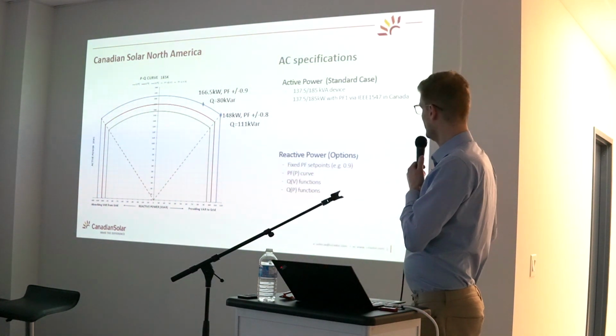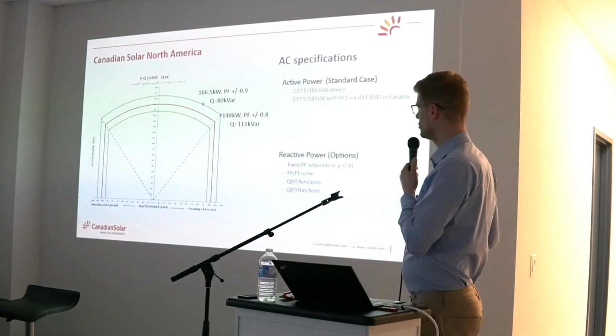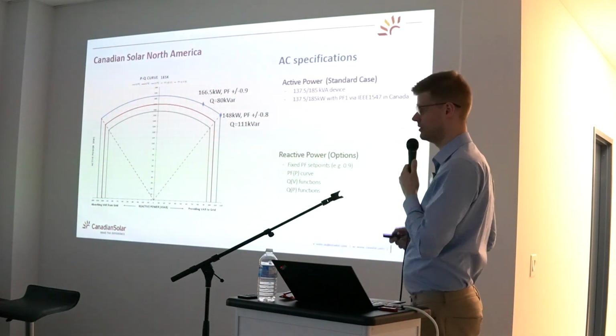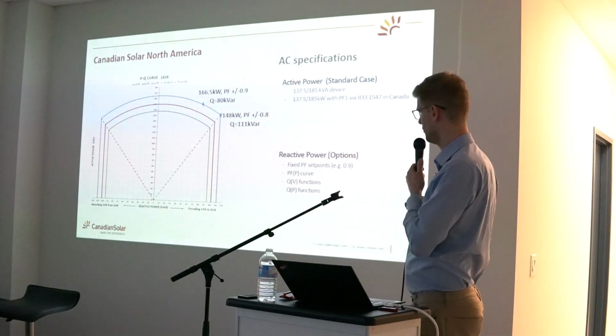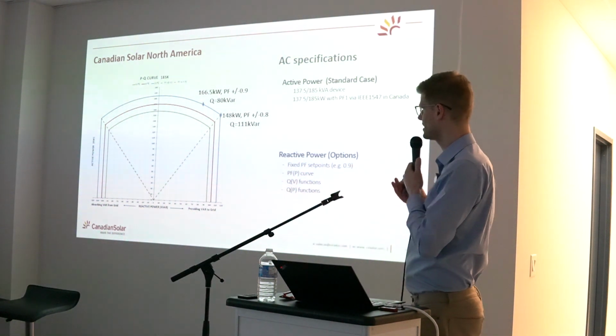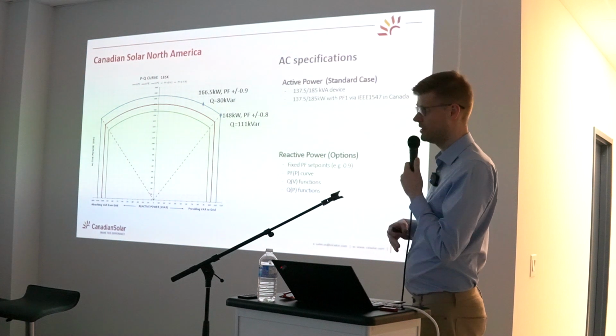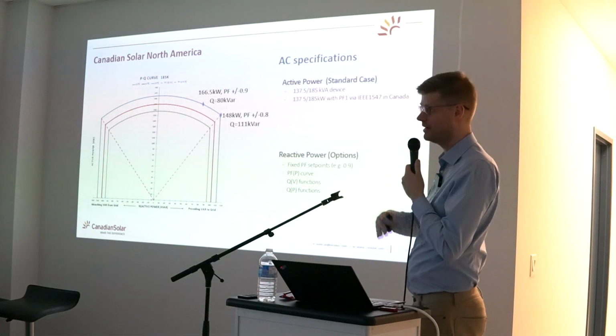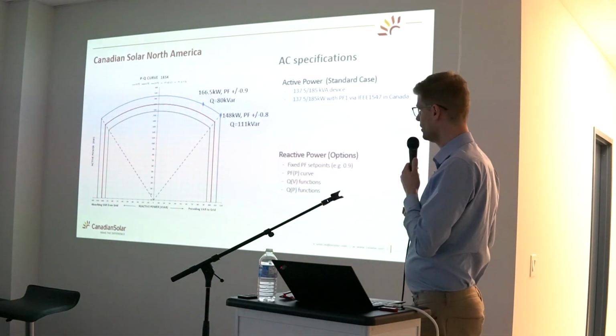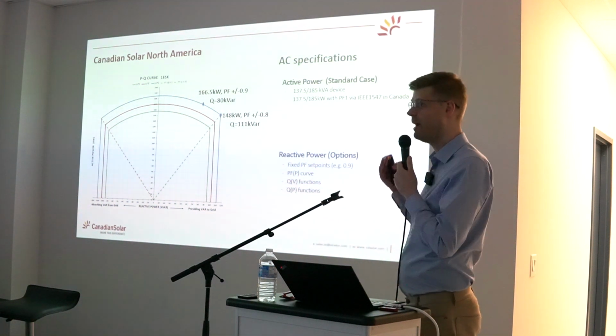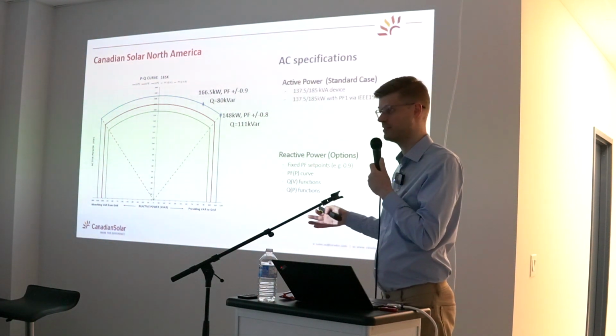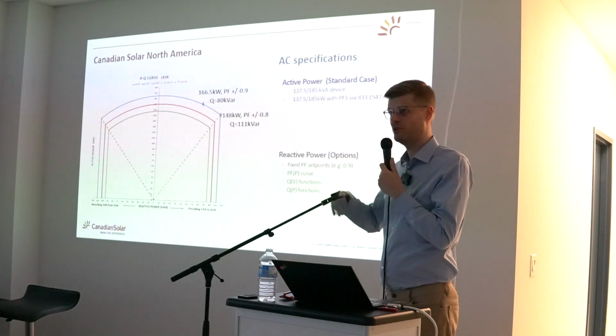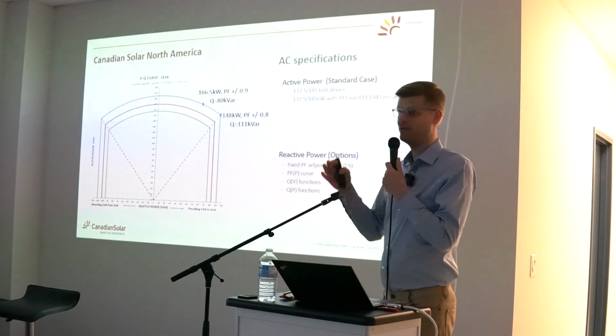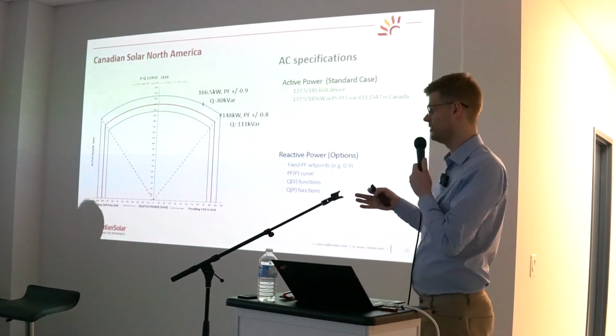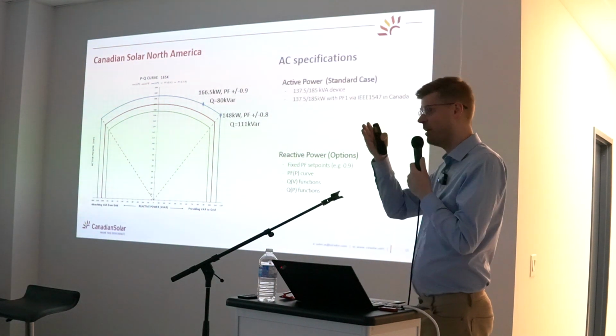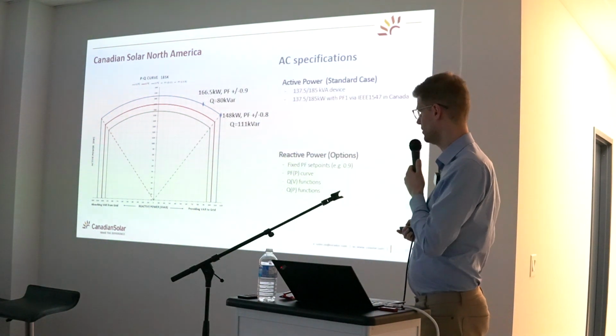The options you have available to use that power factor or that reactive power output are, the first one I just talked about, the fixed power factor setting. So the utility company just tells you 0.9 it is, and you have 0.9 whenever the system is producing. You can also have a power factor that is dependent on the current output power of the unit. For example, up to 50% you're not providing any reactive power, and from 50 to 100% of P nominal of the unit, you provide, let's say, 0.9 as a linear degradation of your curve.